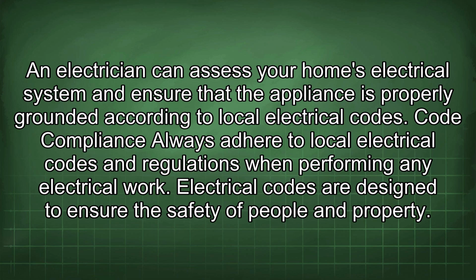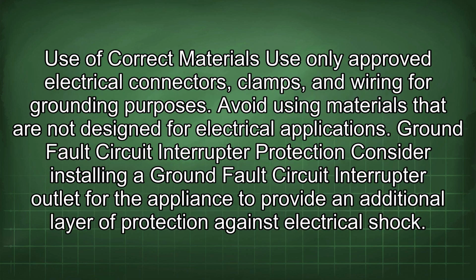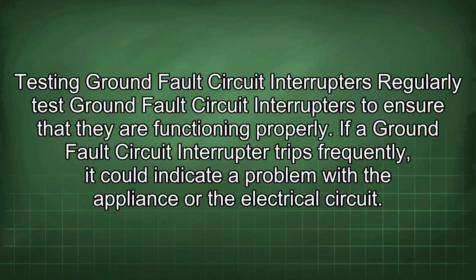Electrical codes are designed to ensure the safety of people and property. Use of correct materials: use only approved electrical connectors, clamps, and wiring for grounding purposes. Avoid using materials that are not designed for electrical applications. Ground fault circuit interrupter protection: consider installing a ground fault circuit interrupter outlet for the appliance to provide an additional layer of protection against electrical shock.